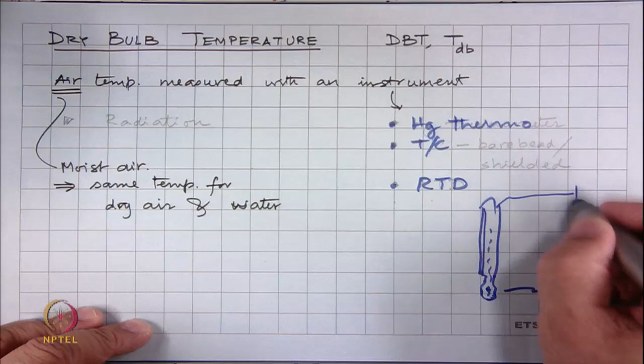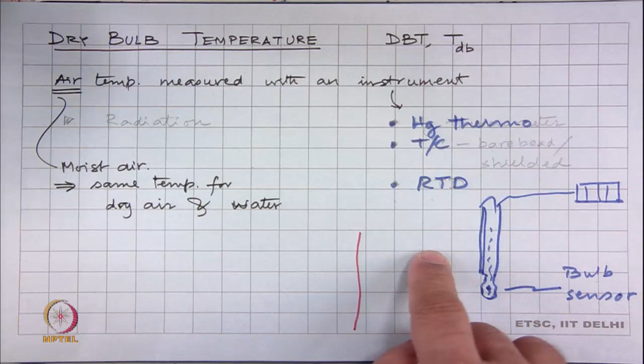What one has to take care about though in this case is that every time we have something anywhere in the air, there is always radiative transfer between the surrounding surfaces and that sensor. So, if we really want to measure only the temperature of air, we need to cut out as far as possible all this radiation that is happening, which means that if there are other surfaces in this vicinity, then we need to make sure that this radiation does not affect this. Because even if there is a small difference in this temperature and say this surface temperature, which could be a wall or it could be the skin of a person or some other engineering device, then this is going to radiate also, and this will show a temperature which is not exactly the temperature of the air.